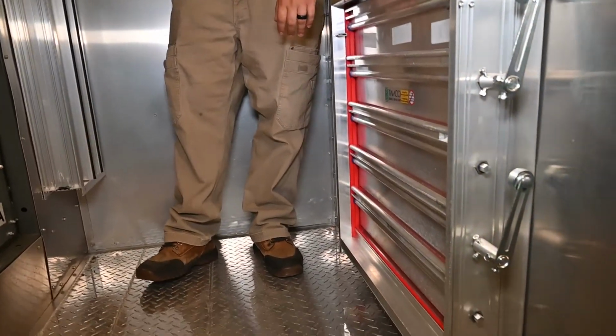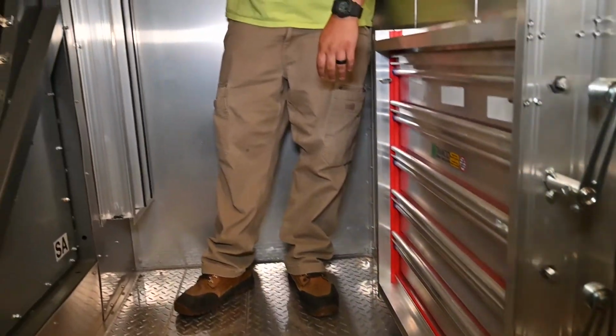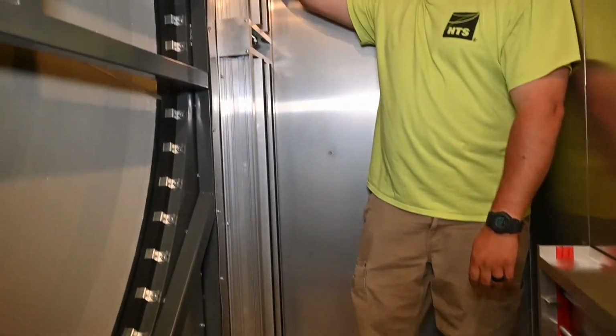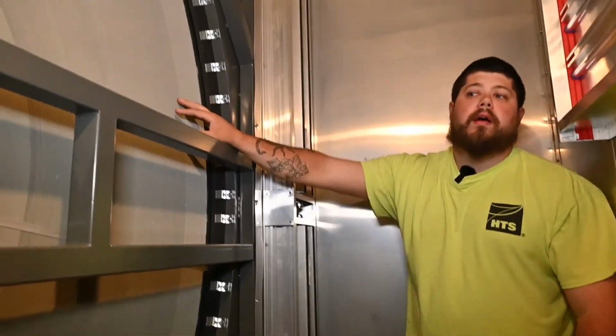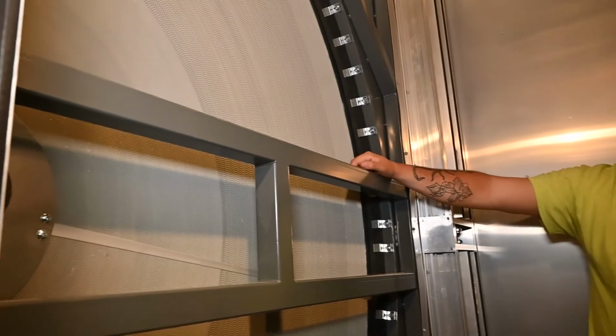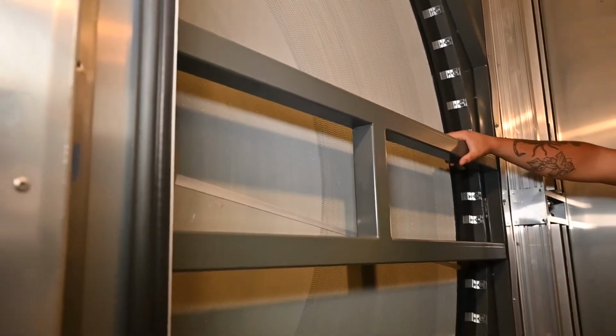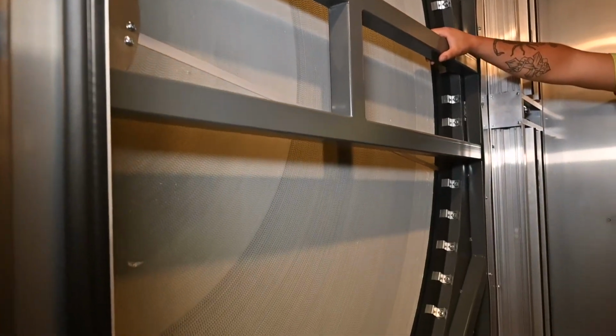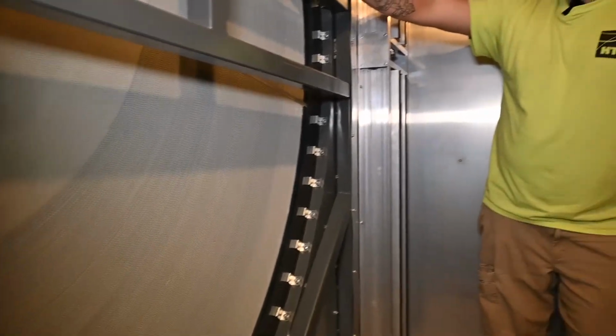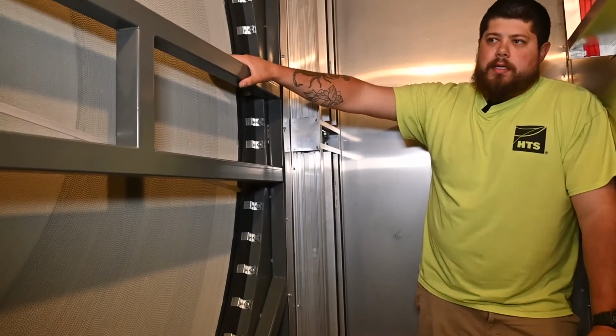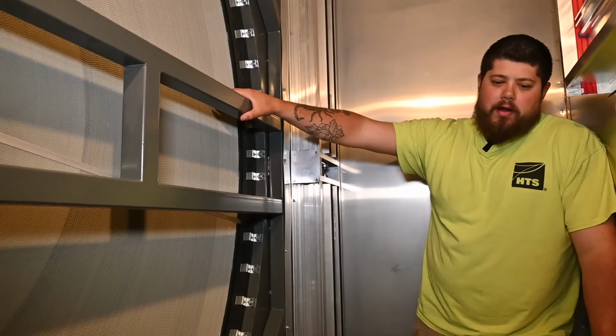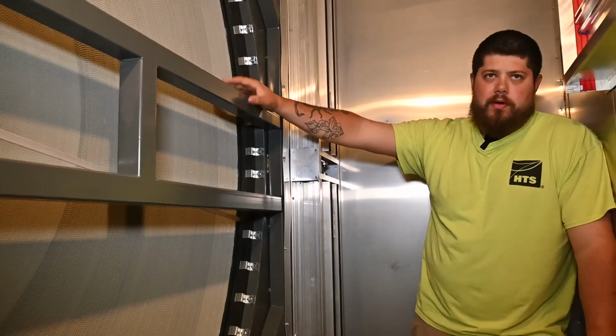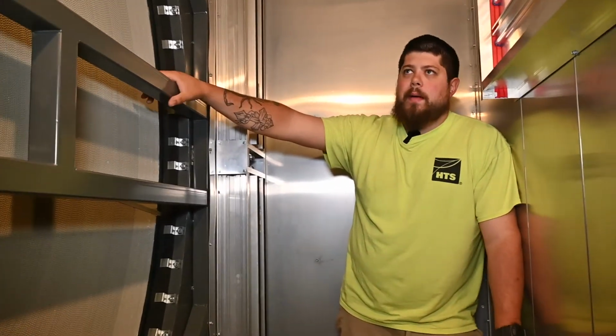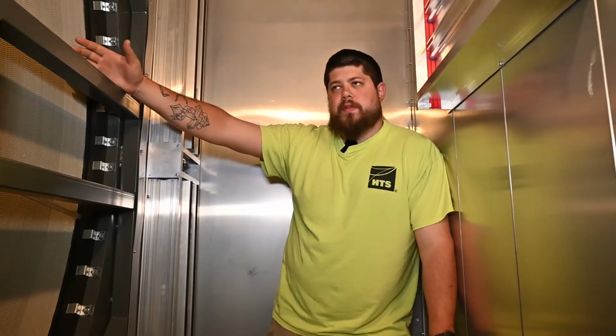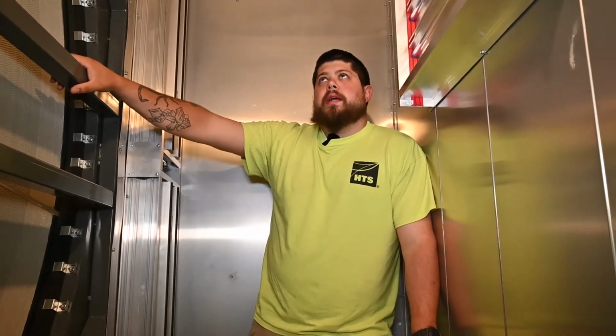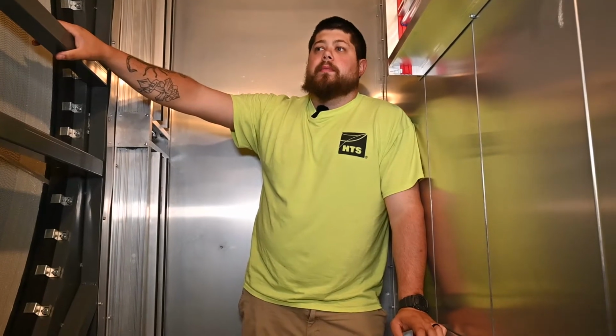Over here, we have a bypass damper that bypasses the heat wheel. And this is the heat wheel itself. The heat wheel is going to have a belt. I don't believe there's any grease spots on the motor. When we get around, I'll take a look, but I'm almost positive there isn't. The belt itself, it's just like any other belt, should be checked periodically. Maybe every 6 months when you go to grease the motor, just check it, bend it, make sure nothing happens to it. If it has signs of corrosion or breaking, then I recommend replacing it.